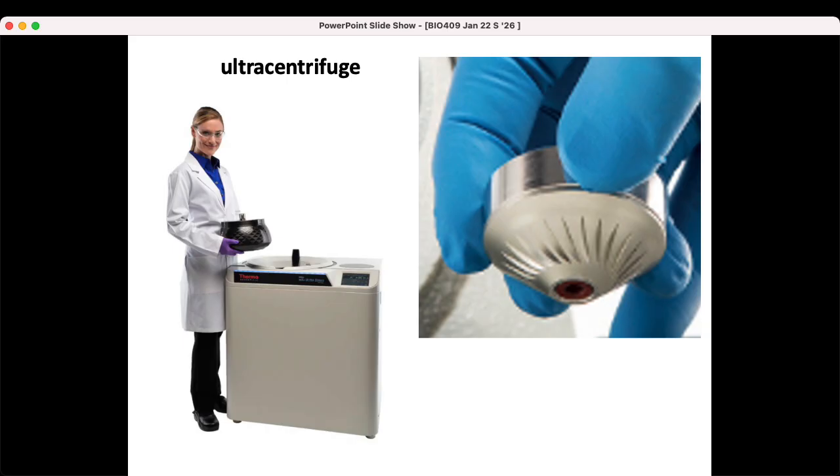And here's a rotor for an ultracentrifuge around that's called an airfuge. And you can see it has the set of parts that's going to spin, has these little fins. And all that's done there is a jet of air is shot at that and it's causing them to spin. That's why it's called an airfuge. And the jet of air is so focused and so fast that this will spin 100,000 revolutions per minute, like that, and just spin a very small sample.